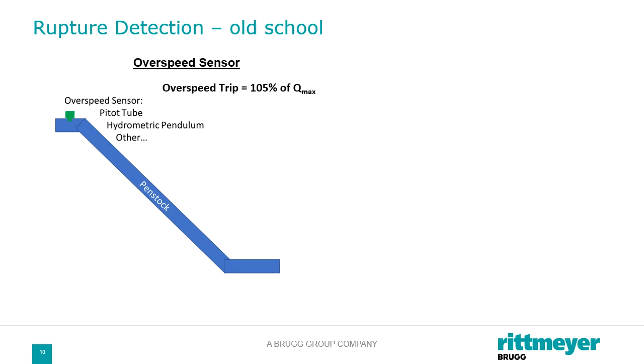I worked with a customer recently who has a 5 or 6 meter tunnel and a pitot tube right at the edge, and it goes into a header of 4 or 6 penstocks. And what they're seeing is that depending on how that header is loaded, if it's just one of the end units it's on, or there's 2 or 3 versus all of them, this velocity sensor may have different readings even if the flow hasn't changed. And so it's led to some nuisance trips in their case, and they've had to set the velocity trip level high enough that it's questionable whether it's really doing any good or not. Now, in other cases, they work actually quite well, but they can be a nuisance from time to time, so keep that in mind.